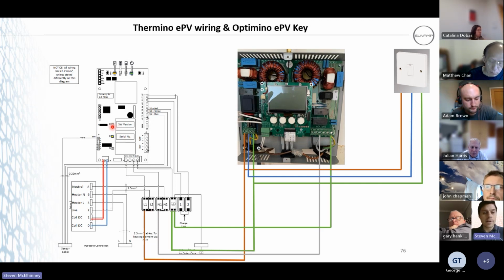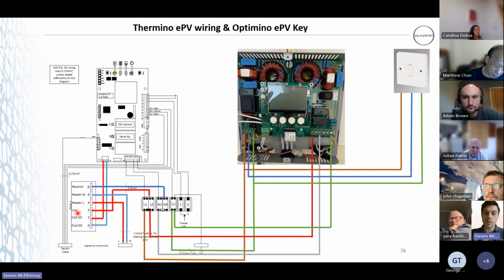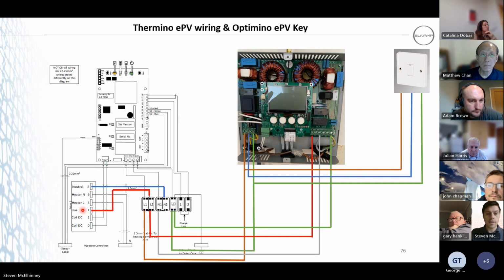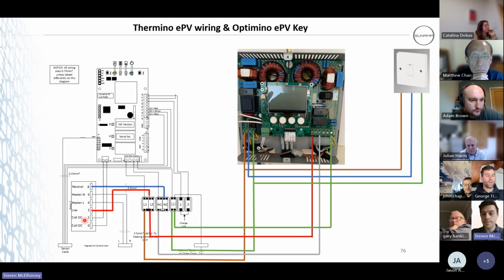The heat battery is detecting a demand for heat, so LED D5 again is illuminated. That's now energized relay 2, but there's no power coming in anywhere. There's no power coming down L2 to then feed that switch to the relay. Once PV's been generated or there's a time boost set, that's when everything starts happening. Your power's now coming down that switch live, the black wire, feeding L2, which is feeding the switch of your contactor. Because the contactor relay's closed, it sends power to your element. Once the heat battery is up to temperature now, LED D5 has gone off, and we've de-energized that coil of the relay. You can still have power coming down here, but it's not going to go anywhere because we've broken the circuit. That makes sense? How's everyone finding that?